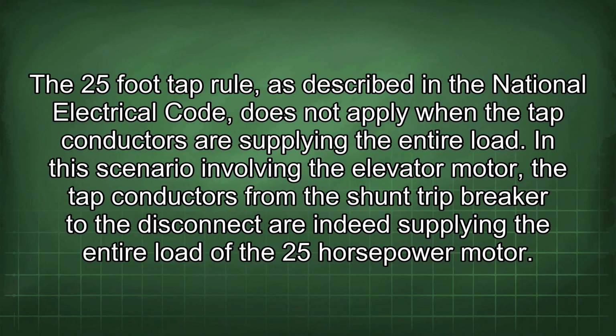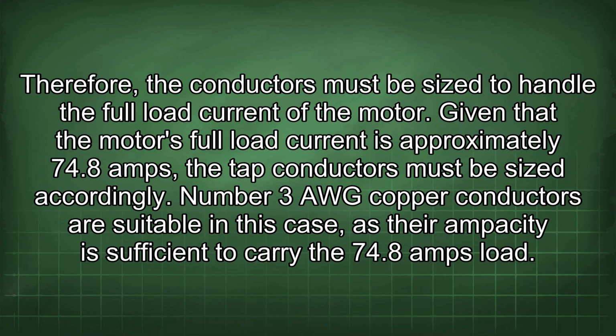The 25-foot tap rule, as described in the National Electrical Code, does not apply when the tap conductors are supplying the entire load. In this scenario involving the elevator motor, the tap conductors from the shunt trip breaker to the disconnect are indeed supplying the entire load of the 25 horsepower motor. Therefore, the conductors must be sized to handle the full load current of the motor.